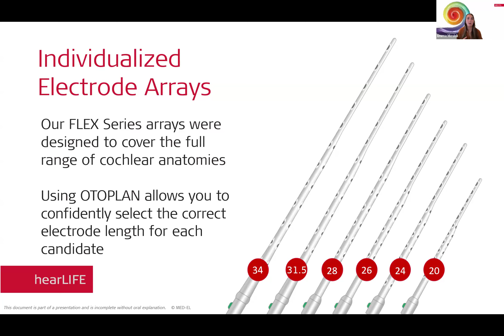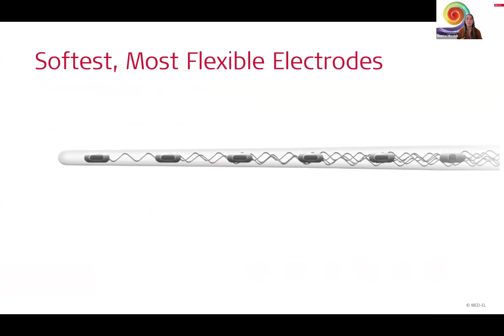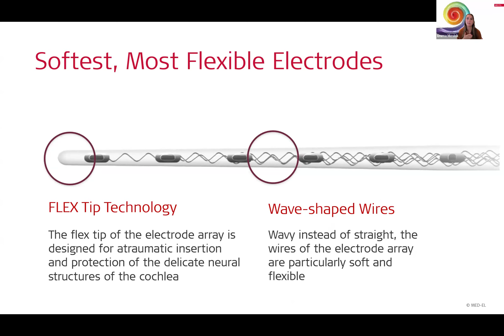So other than us having all of these individualized electrode lengths, our electrode is going to be soft and flexible. Two factors of this: first, the Flex tip technology, so it's really going to go in smoothly and make sure that we're having structure preservation. As well, we have all of these wave-shaped wires in the electrode array, and that really ensures that as the electrode goes into the cochlea, it's conforming to the shape of the individual cochlea. So it's following the path rather than pushing through.